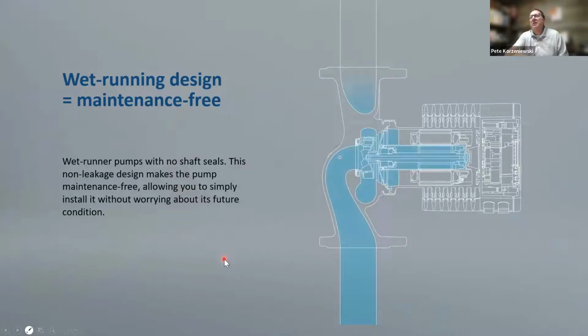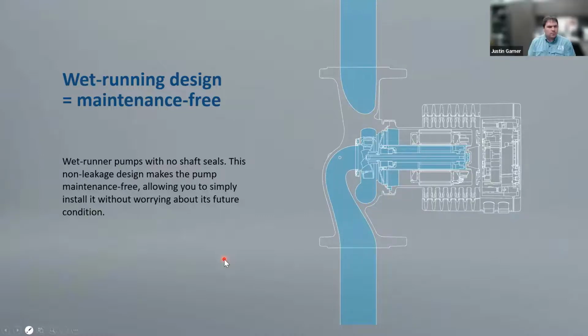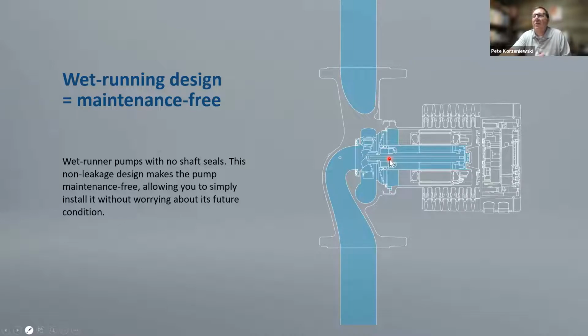One of the things to know about these distributed pumps, at the size ranges that we're talking about, is they're wet rotor pumps. People who design smaller heating systems are pretty familiar with this terminology. Others that spend more of their time on the chilled water side may not be aware of this. Basically, a wet rotor pump utilizes the pumped liquid to circulate around the motor shaft to remove any heat generated by the electric motor. There is no separation between the pumped liquid and the motor electronics, which is normally the job of a mechanical seal in a traditional pump. So we don't have that mechanical seal. We don't have bearings that we need to worry about. So those wear parts, the moving parts that are typically the most common failure points within a pump, are not there. The pumps are essentially maintenance free and oftentimes last well beyond the expected life cycle of the system that they're put into.